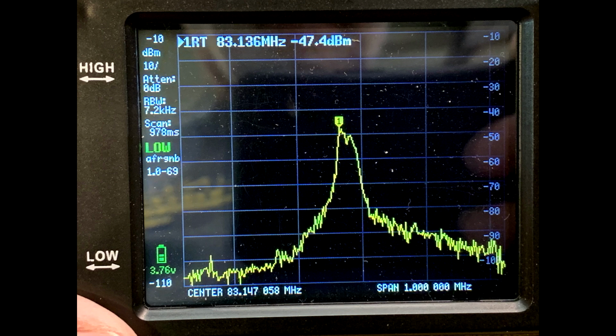So he suggested that I try lower attenuation levels. Take it out of auto mode, put it into manual mode, and try different attenuations. He also suggested some other settings. There are some gain settings in the expert configuration menu. I don't want to touch those yet. I will eventually, but I think they'll probably get a lot of people into trouble. The only people who are going to be touching really weird settings are going to be pretty sophisticated users already. I want to address the users that just want to use the spectrum analyzer easily and not have to think too much about it. They're not experts.